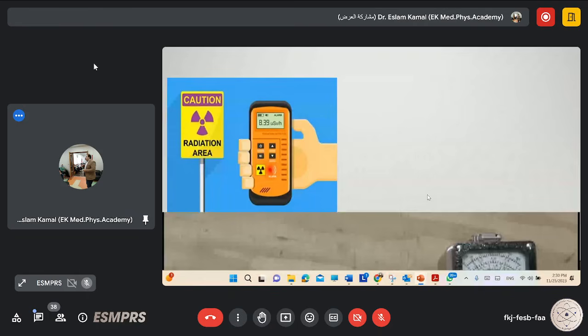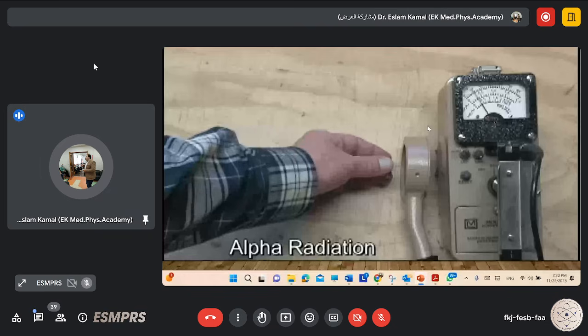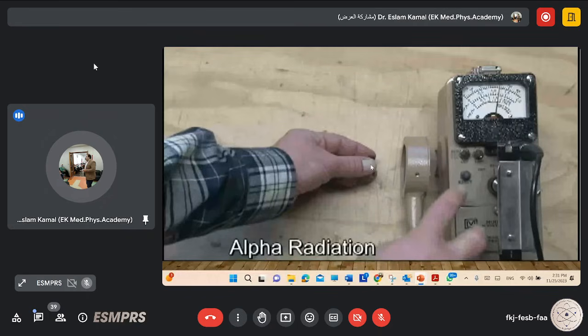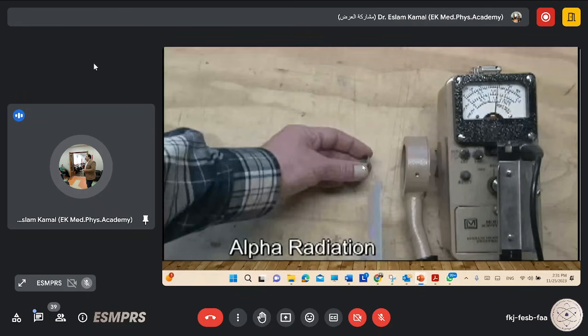As you can see here, there is a good example for detection of different radioactive sources. We have here alpha radiation, and we have here a pancake survey meter. This pancake survey meter is highly sensitive in detecting radiation. This is our probe, or our detector. If you move the alpha source close to this probe, you will find this arrow going up. That means more radiation is being detected from this alpha source. But to stop the alpha particles, you can use only a thin sheet of paper. At that time, all alpha particles will be stopped here, so they will not penetrate the paper to reach our detector. So you will find the arrow goes down because of that.